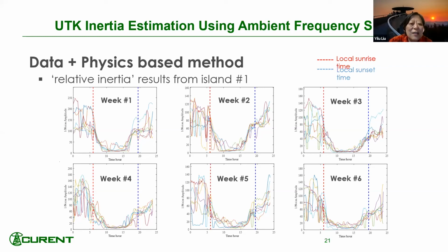I have very good confidence we can operate a power grid with zero inertia, and this is one proof. Though it's a small island, it's operating 100% renewable much of the time, especially during good weather, for quite a long stretch—maybe 5 hours—with almost zero inertia, across 6 different weeks, and their patterns are very consistent. This is what the grid will look like.